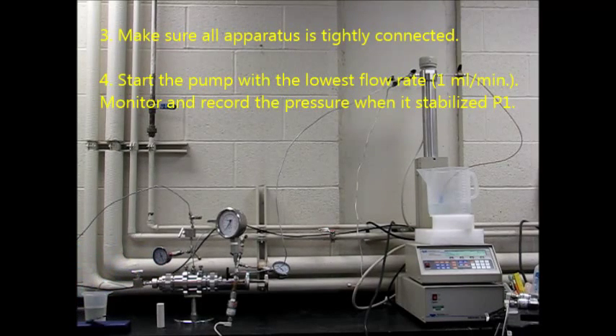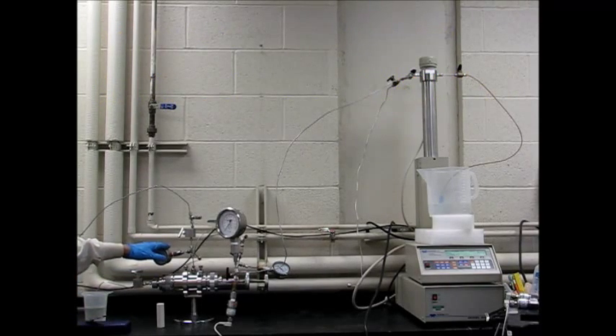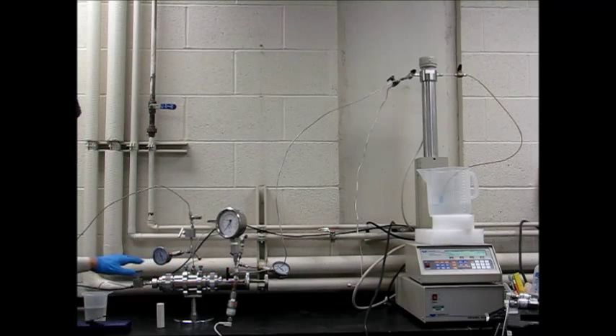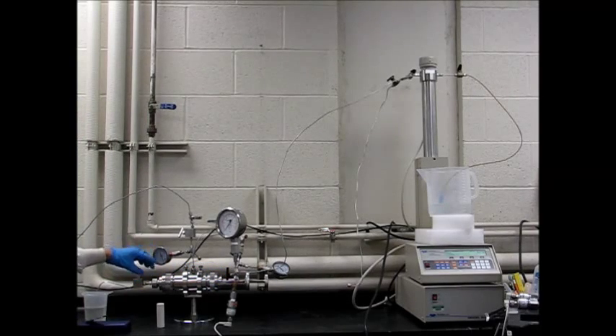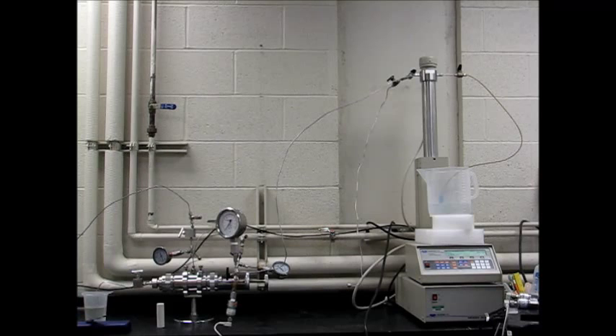Number three, make sure all fittings are tightly connected, otherwise you might have a leak and that will lead to inaccurate measurements. Number four, start the pump with the lowest flow rate, which is 1 milliliter per minute, then monitor and record the pressure when it's stabilized. Record P1 and P2.